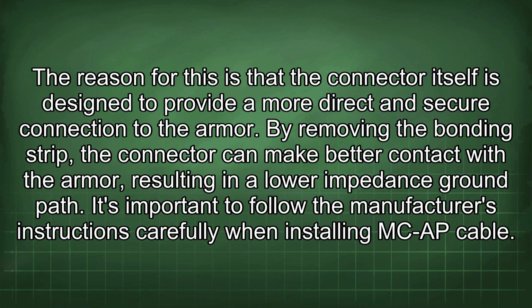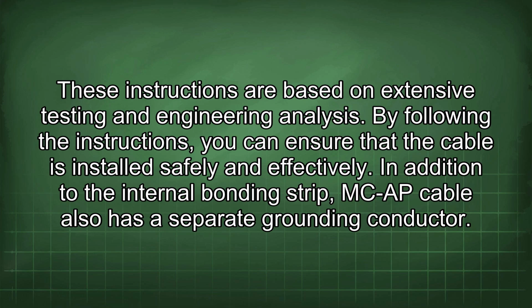The reason for this is that the connector itself is designed to provide a more direct and secure connection to the armor. By removing the bonding strip, the connector can make better contact with the armor, resulting in a lower impedance ground path. It's important to follow the manufacturer's instructions carefully when installing MCAP cable. These instructions are based on extensive testing and engineering analysis. By following the instructions, you can ensure that the cable is installed safely and effectively.